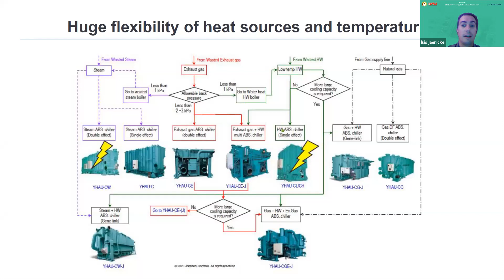In a typical scenario with a gas engine, for example, where you have energy coming out of the exhaust gas and also a lot of energy coming out of the jacket water, you can have a one-to-one configuration, one engine, one chiller. The chiller can take exhaust gas plus hot water, or steam plus hot water, coming out of the engine. In the case of fuel cells, we can also take the exhaust from the fuel cells, or the hot water, as some fuel cells supply hot water as a byproduct. So as a summary, a very large portfolio of absorption chillers able to fit any kind of power generation equipment in a cogeneration plant.